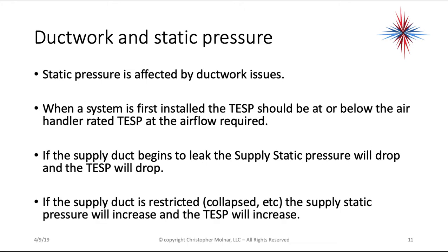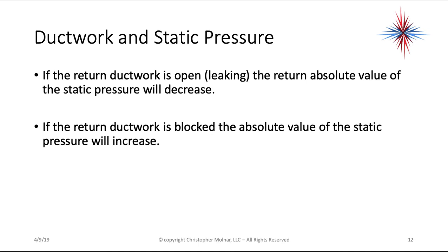Static pressure is affected by ductwork issues. When a system is first installed, the total external static pressure should be at or below the air handler rated total external static pressure for the required airflow. If the supply duct begins to leak, the supply static pressure will drop and the total external static pressure will drop as well. If the supply duct is restricted — such as a collapsed duct or too many registers closed — the supply static pressure will increase and so will the total external static pressure. If the return ductwork is open or leaking, the absolute value of the return static pressure will decrease. If the return ductwork is blocked, the absolute value of the return static pressure will increase, as it is trying to pull a harder suction.